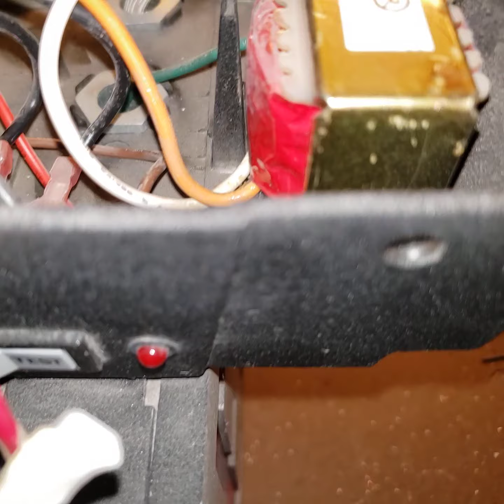But this one doesn't have a secondary, so they can't use that to power my LED. This is a unique transformer because it's called an autotransformer - there's only one winding. You'd still have a neutral and a hot, but in this case you could also put 270 volts into it and get 120 out, or in theory put 120 in and get 270, or rather 277, out of this thing. I'm just rounding it, incorrectly I guess.